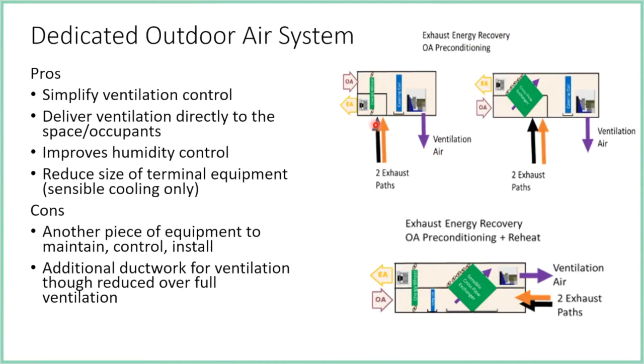In the case of a summer requirement, this air that's coming through here is, we'll call it 72 degrees and 50% relative humidity. And this outdoor air might be, you know, 95 degrees and 60% relative humidity. So it's quite warm and quite humid. And again, that heat is transferred back to the exhaust stream, and the coolness that's coming from the return air is transferred to the, well, heat only moves in one direction, coolness is actually transferred. But the heat from the outdoor air is transferred to the exhaust air, which means it's getting a pre-cooling effect before it hits the cooling coil, again, making this entire unit quite efficient.